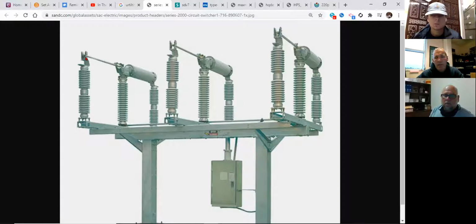This is the physical connection right here that goes all the way through the interrupter tube. So you're going to have a wire coming out of the back, and you're going to have a conductor coming out of the front right here. SF6 is the normal means of load break inside this tube right here, but it's meant to not only interrupt normal load on a circuit, but also fault load on a circuit. And we know fault load can be extremely high.